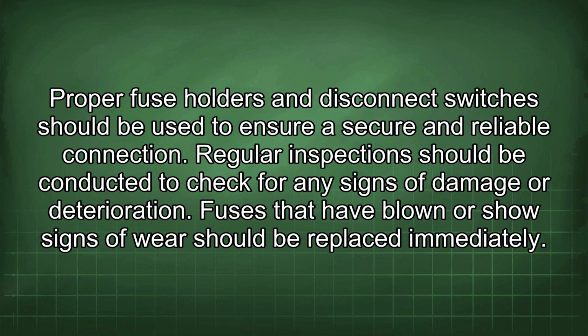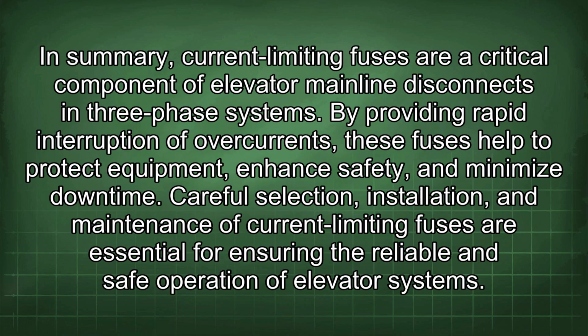Proper fuse holders and disconnect switches should be used to ensure a secure and reliable connection. Regular inspections should be conducted to check for any signs of damage or deterioration. Fuses that have blown or show signs of wear should be replaced immediately. In summary, current limiting fuses are a critical component of elevator mainline disconnects in three-phase systems. By providing rapid interruption of overcurrents, these fuses help to protect equipment, enhance safety, and minimize downtime.